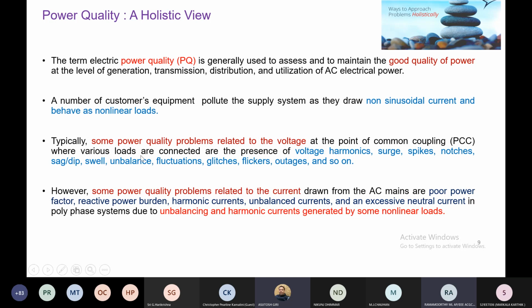So basically there are two kinds of power quality related problems. One is related to voltage, and voltage problems are like harmonics, surge, spikes, notches, sag, dip, swell, unbalance, fluctuations, glitches, flickers, and outages. These are voltage related power quality problems. And some power quality problems are related to current, like poor power factor, reactive power burden, harmonic currents, unbalanced currents, and excessive neutral current in polyphase systems.